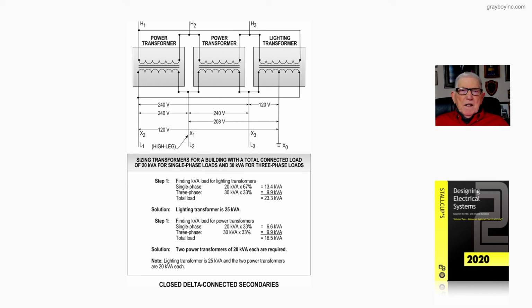But typically they would take all 3 and add them together at 25 kVA each, add those three 25 kVAs together, you'd come up with 75 kVA, and take 58% of that, and you could use that value of 58% times the 75 kVA and feed other loads with that amount of current that would be available to you. And basically that's what this figure 20-2A is illustrating.